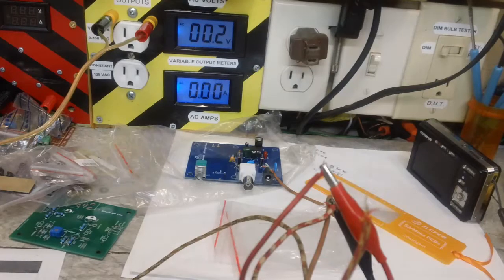Like I said, this should be the high voltage winding, so it should go up pretty quick. We'll go up to 10 volts, roughly. At 10 volts, I have 48 on the windings I'm monitoring, the red and the red-white.